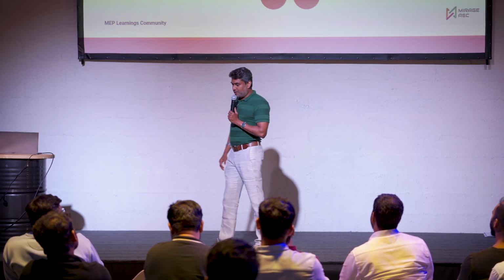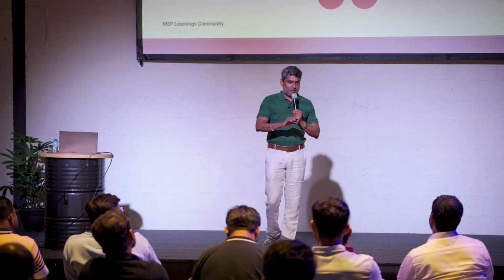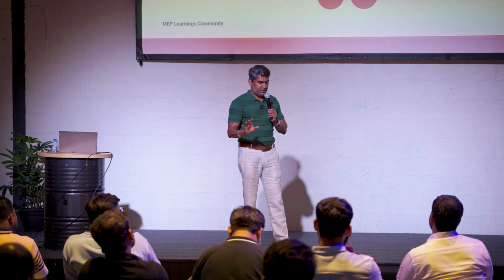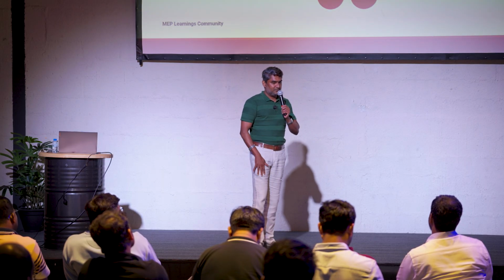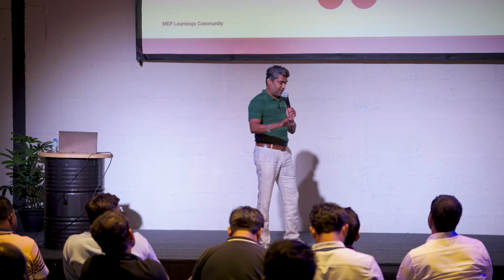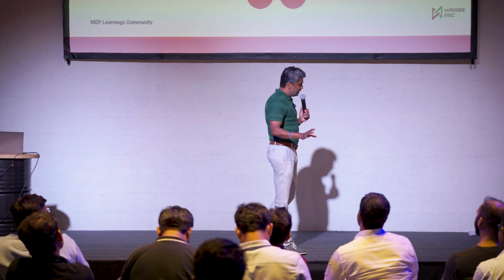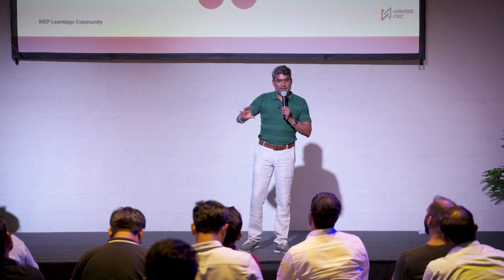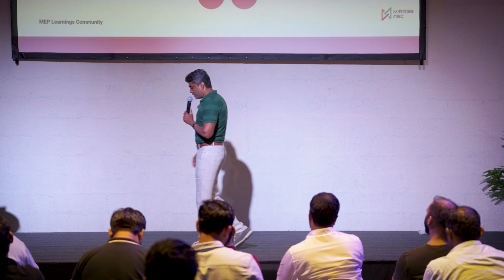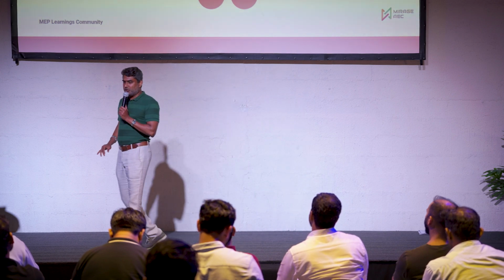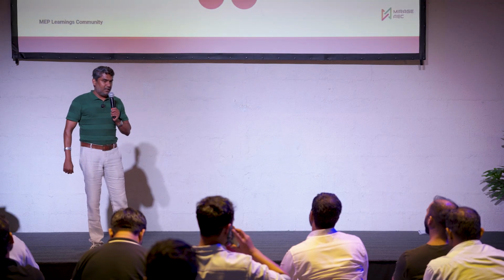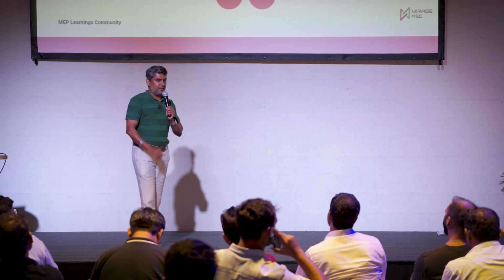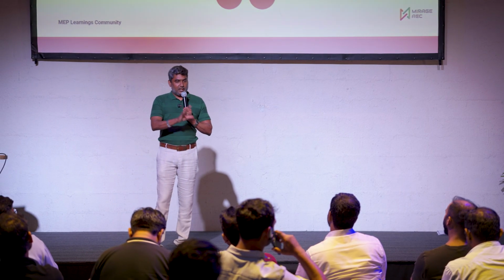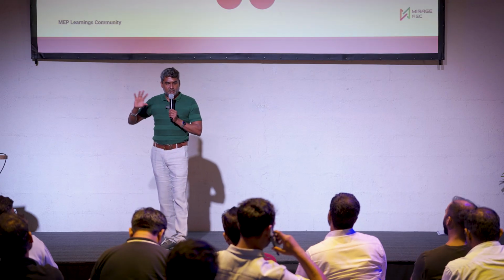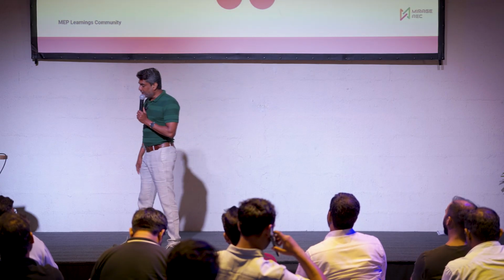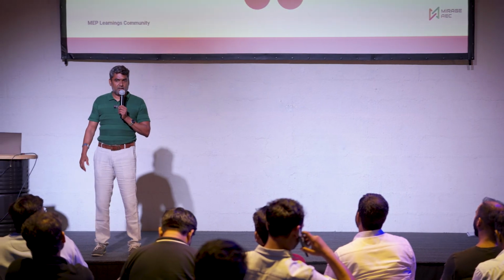Okay, but actually the fire alarm system does not switch on the fire pumps. It just monitors it. The fire pumps actually operate on their own. They have their own controls, their pressure sensing. So based on that, it will switch on. But still, the fire system will monitor the fire pump, so that when the fire pump is running, it knows that there is something wrong, or there is an event in the building. So that's the reason it is interfaced.